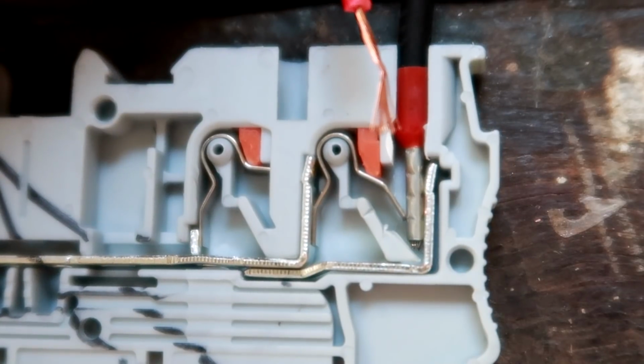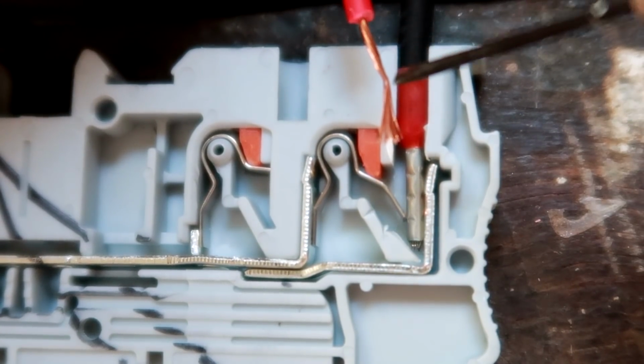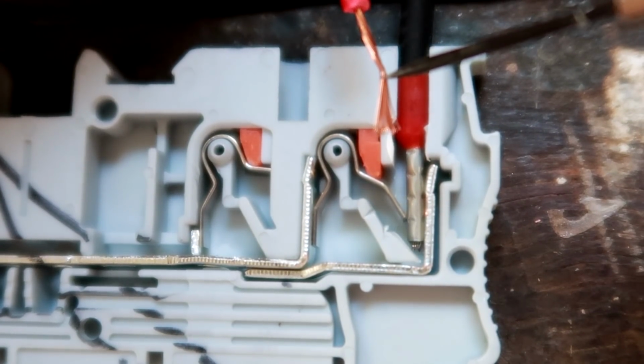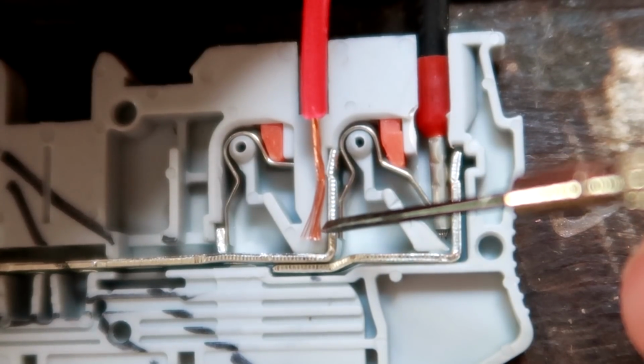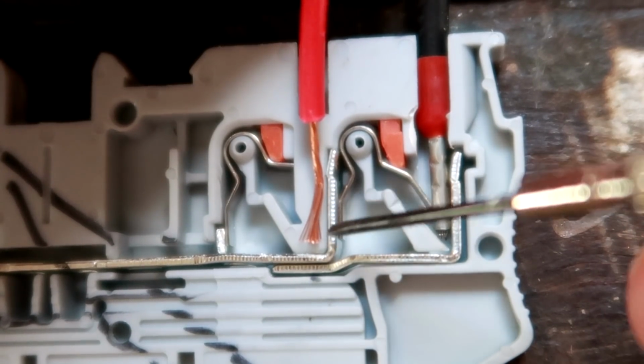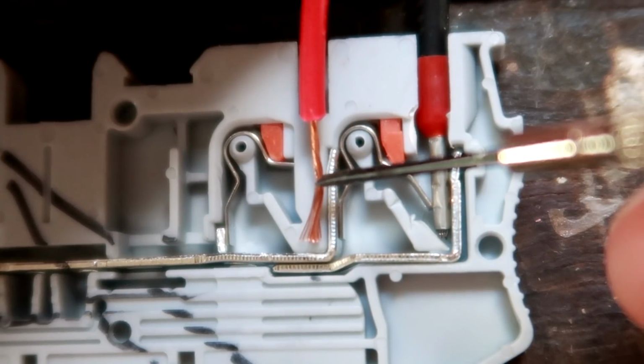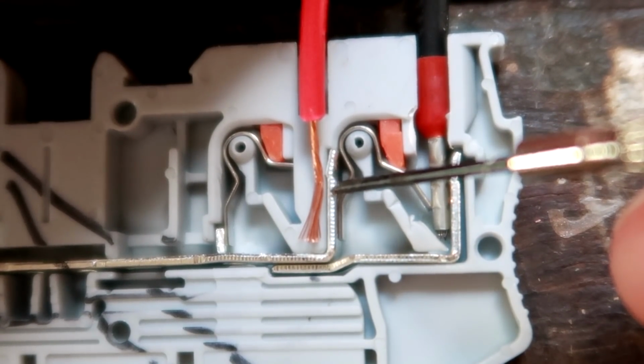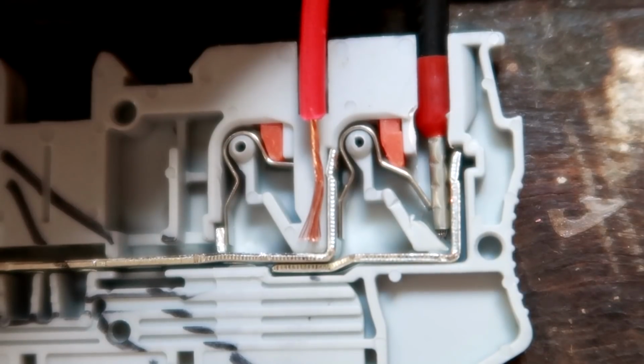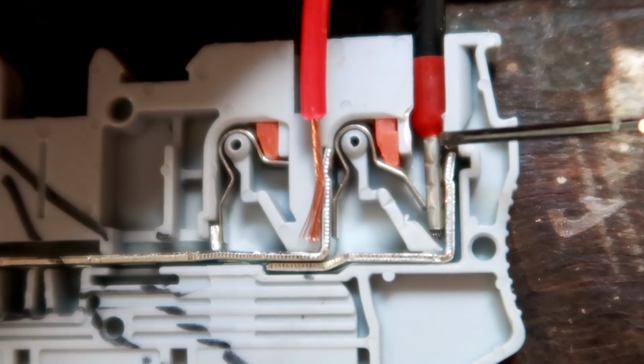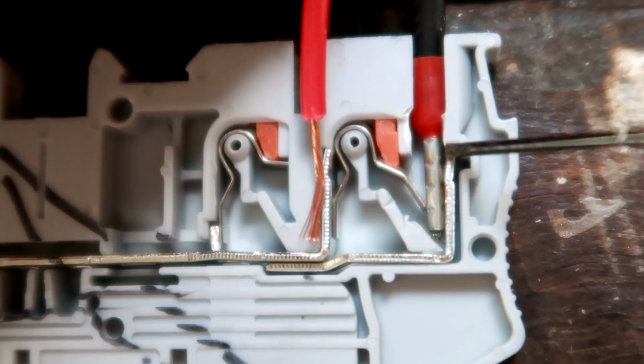Here's a comparison: you can see the cable we just used gets pinched at this one location, and the bottom of the cable points away from the bus bar, as does the top. It's only connected via one little contact area to the actual contact inside the terminal. While here, with the ferrule, we have a full length of contact area.